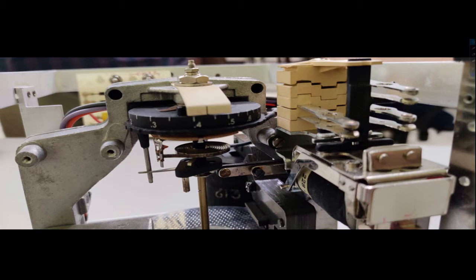Here you see, this one is actually the spindle of the disk. When the disk starts rotating, this spindle also starts rotating. And here you see, this is the normally open switch. This normally open switch is actually connected to the tripping coil. So when the switch becomes closed, only then will the DC power come to this solenoid type tripping coil and energize it. Okay. So there is also one normally closed switch.